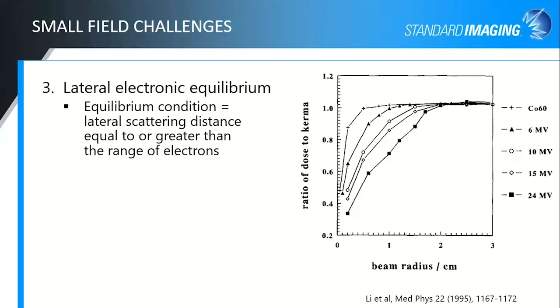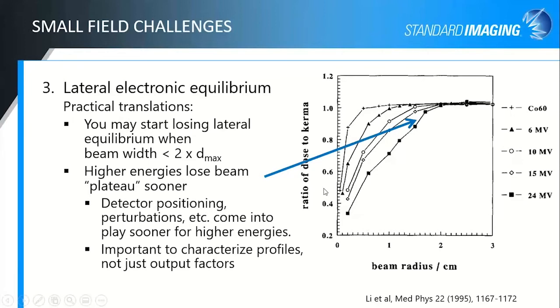The next challenge, lateral electronic equilibrium. Generally, the equilibrium condition is when your lateral scattering distance is equal to or greater than the range of the electrons that are generated by that energy beam. Practical translation of this definition is that you may start losing your lateral equilibrium when your beam width is less than 2 times your Dmax. And this is not really counting the size of your detector just yet, because if you're changing the fluence with your detector, that exact equilibrium condition width may change slightly, but it's a good rule of thumb to start with.